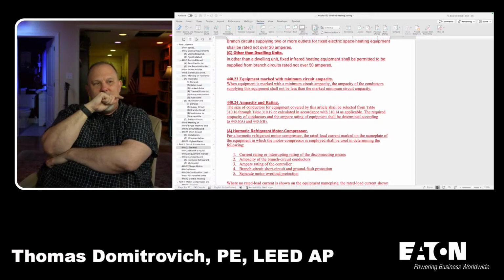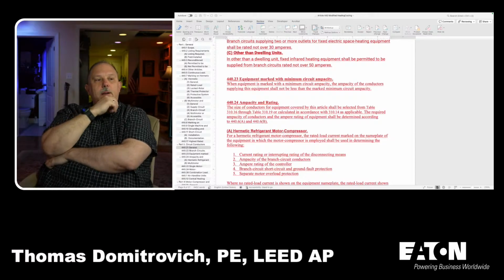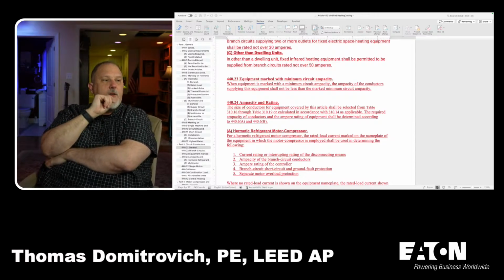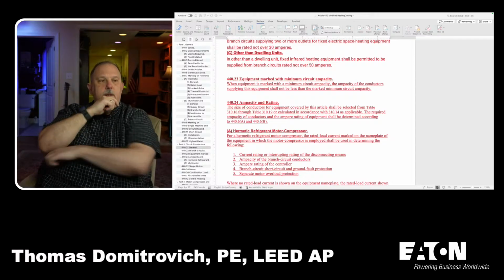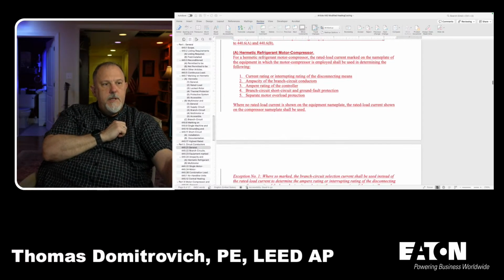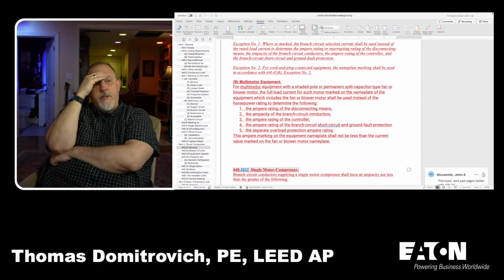It's about time. Yeah. The size of conductors for equipment covered by this article shall be selected from Table 310.16 through 310.19 or calculated in accordance with 310.14 as applicable. The required ampacity of conductors and the ampere rating of equipment shall be determined according to 440.6(A) and 440.6(B). A is your hermetic, and B is your multi-motor equipment.